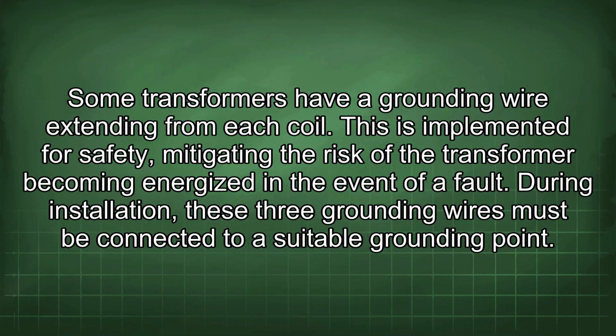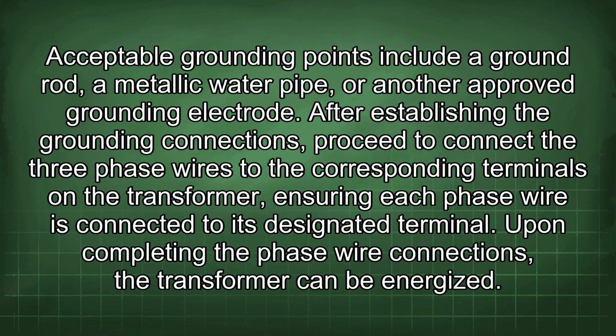Some transformers have a grounding wire extending from each coil. This is implemented for safety, mitigating the risk of the transformer becoming energized in the event of a fault. During installation, these three grounding wires must be connected to a suitable grounding point. Acceptable grounding points include a ground rod, a metallic water pipe, or another approved grounding electrode.